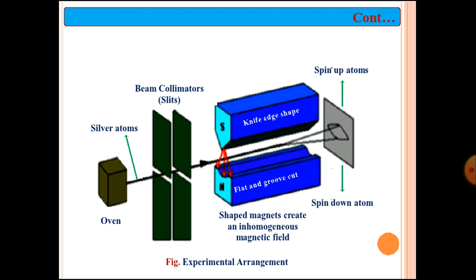A high degree of non-uniformity in the magnetic field is produced by making one of the pole pieces of a powerful electromagnet a knife edge shape and the other flat with a groove cut in it opposite the knife edge. The lines of force are close together at the knife edge and the field there is much stronger than that at the other pole piece. The field is at right angles to the direction of movement of the atoms.